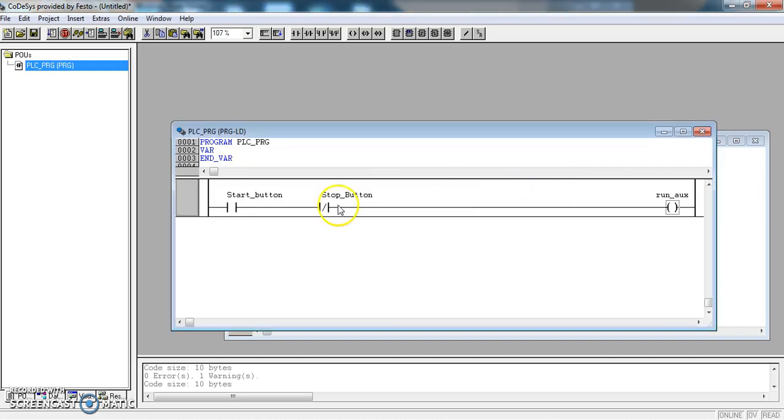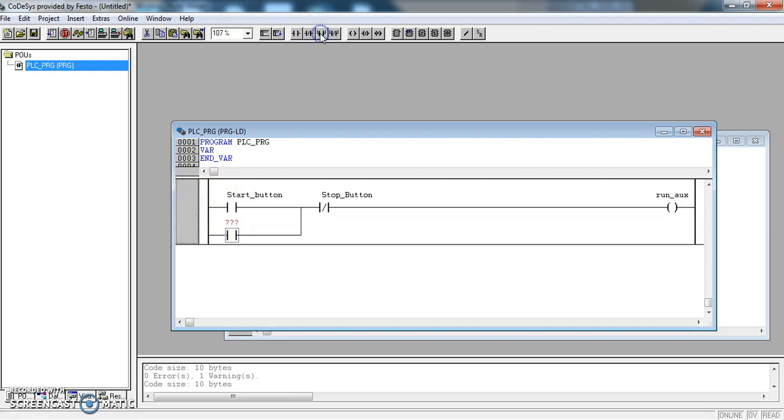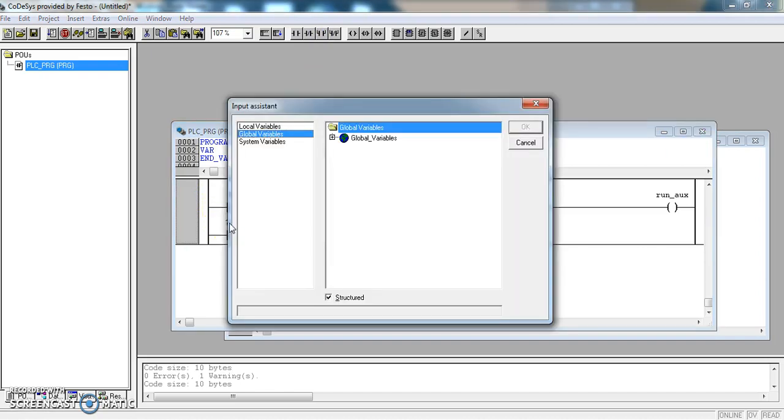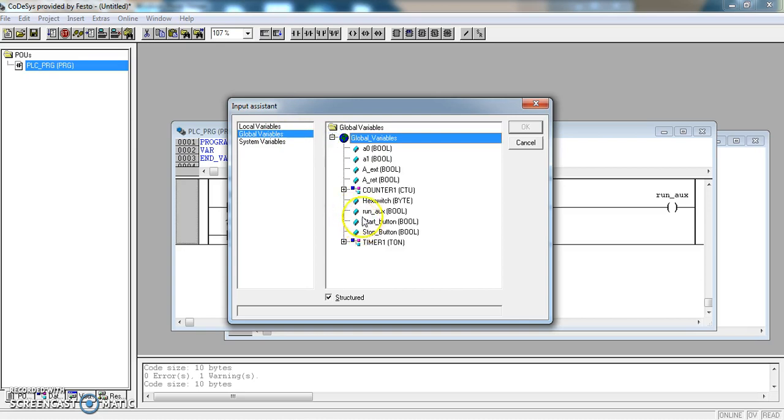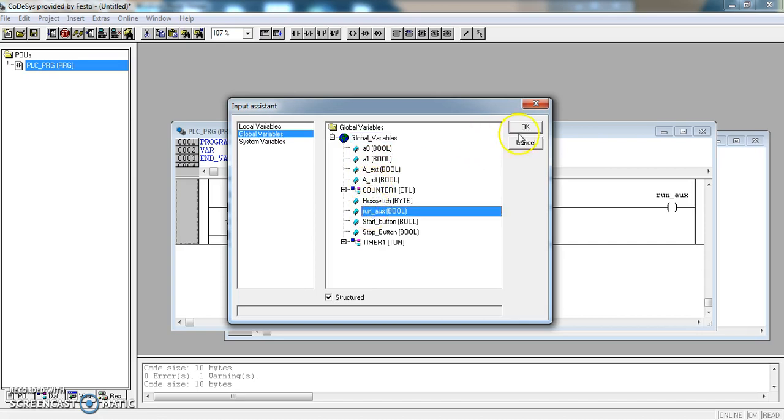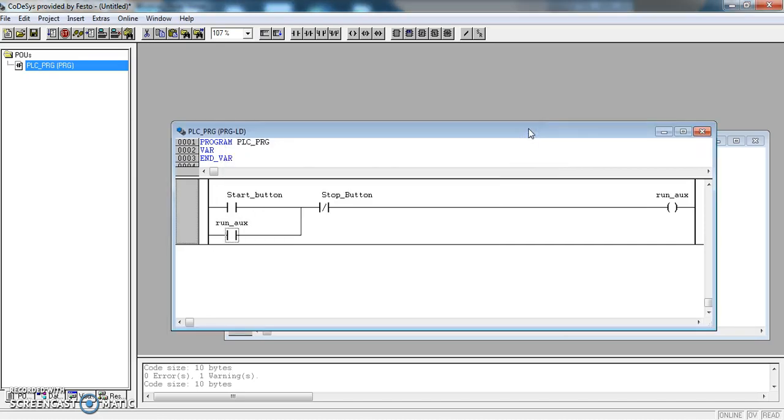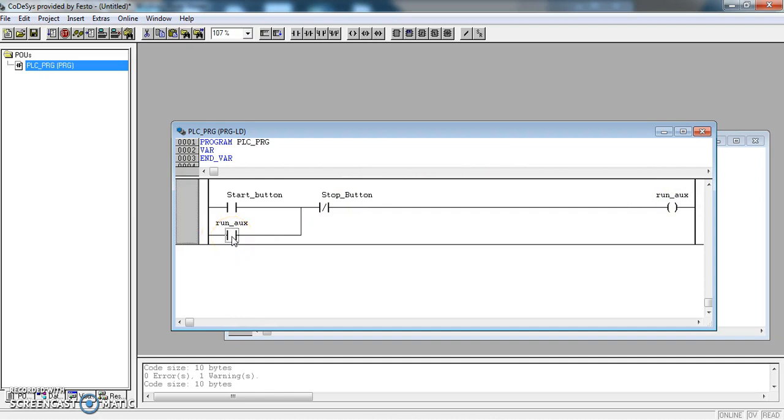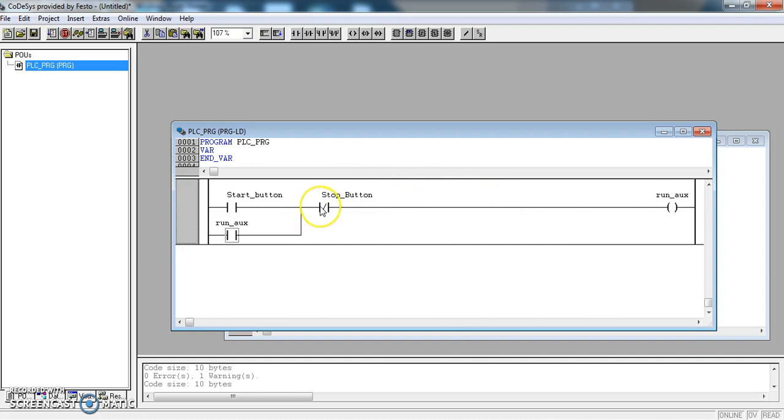And then I am going to self-latch that auxiliary by adding a parallel rung and make that link to the run_aux. So now if the start button is pressed, run_aux will come on. This relay will close, contact will close and the run_aux will stay on until the stop button is pressed.